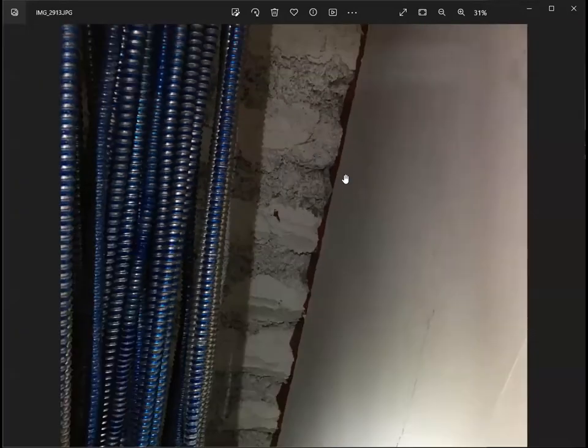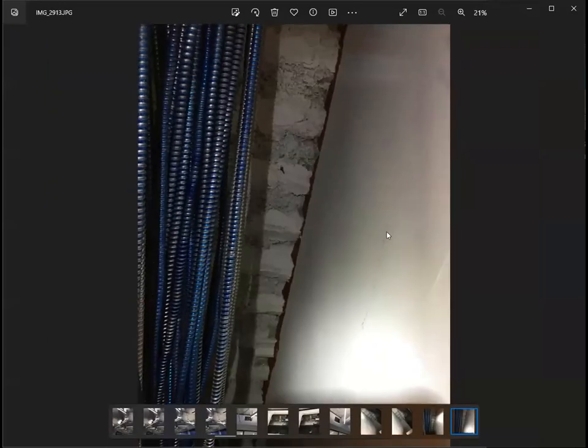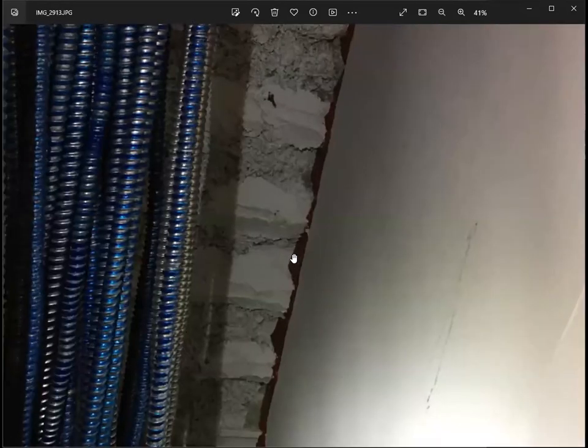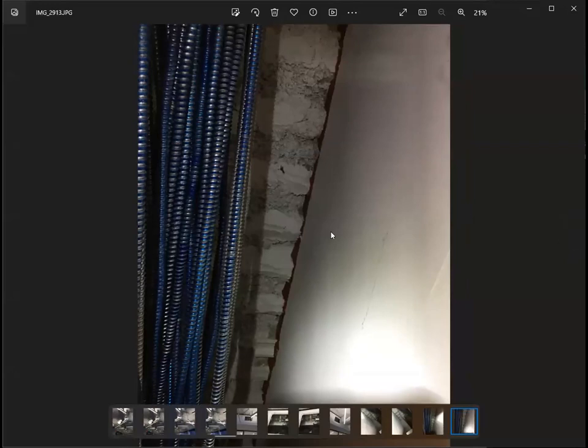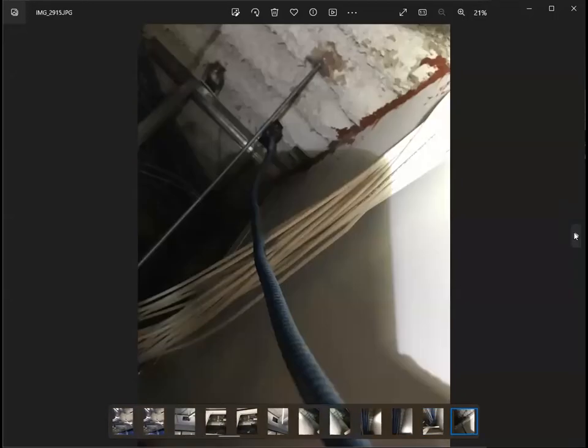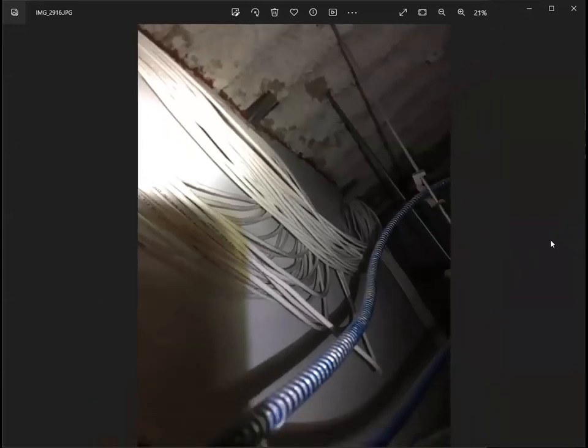This is fireproofing on the ceiling. And as you can see, there is fire stopping against the wall. Oh, is there fire stopping or is it an open hole? So if you see an open hole, you need to verify if this wall is rated between this room and the other side of the room. So if it's a rated wall, this is not acceptable. If it has an open gap like this, it should be fire stopped or fire caulked. It should have a fire caulk material. And every penetration so far.